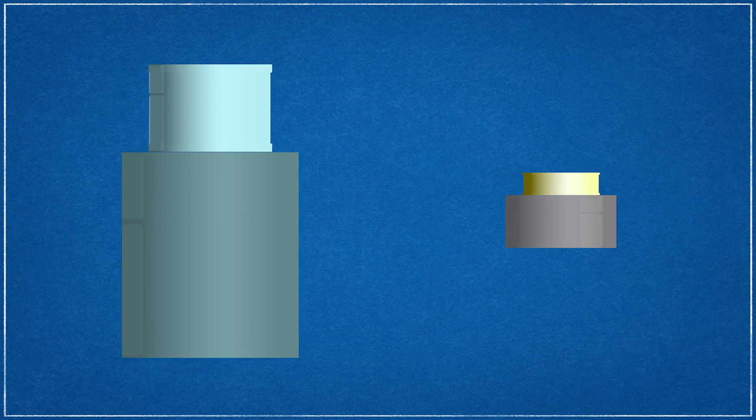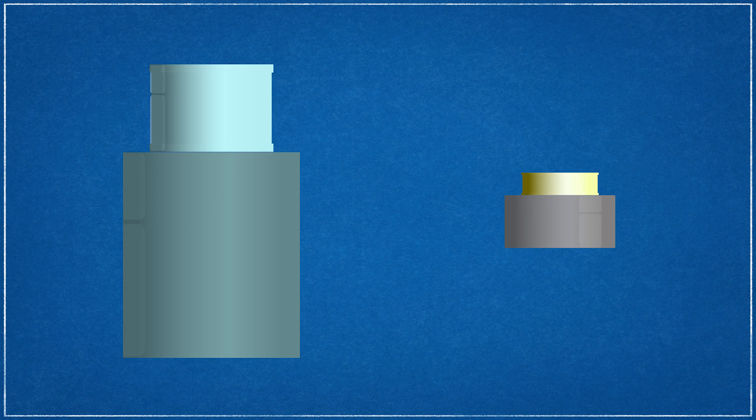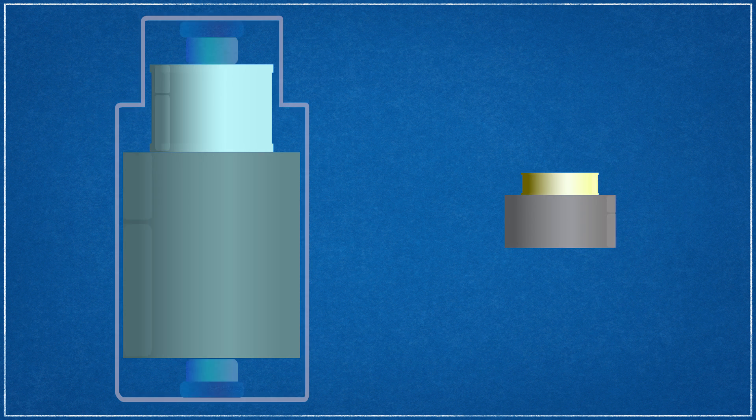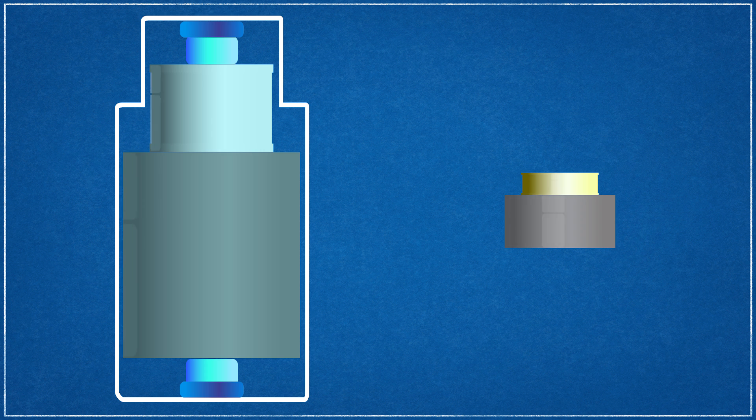Flywheel energy storage system designs generally fall under one of two strategies. Low-speed flywheel systems that operate under 10,000 RPM and high-speed variants that can approach 100,000 RPM. Low-speed flywheels are usually made of heavier, metallic materials and are supported by either mechanical or even non-contact magnetic bearings that support the load with magnetic levitation. High-speed flywheels typically use lighter, stronger composite materials and require magnetic bearings.